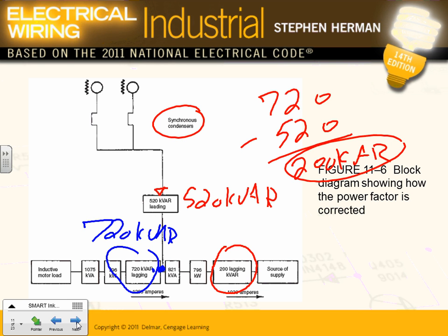Can you guys see that? Right at this point, when you added them, these came in here. They knocked down this number only. They reduced it, and by reducing this number, if you look at the kW, it stays the same. Can you guys see the kW? Where is it? The kW here stays the same. The only thing that changes is the VAR, and because the VAR changes, the kVA has to change. So this went from 1075 down to 821. You corrected your power factor to, what is it, 97, in that example.